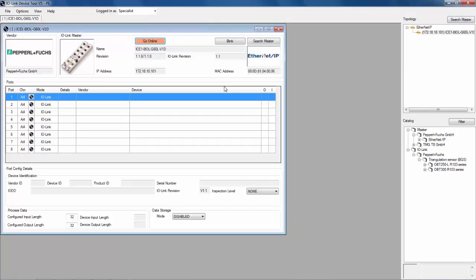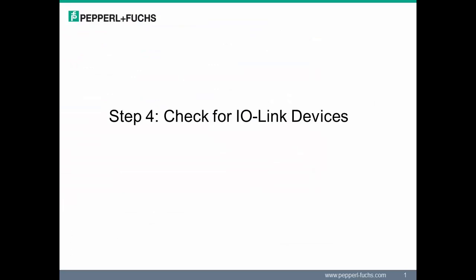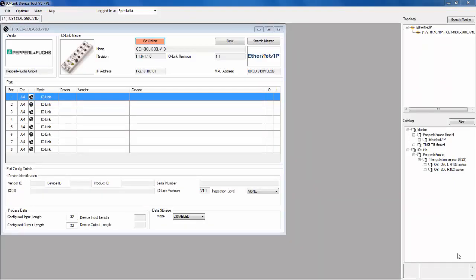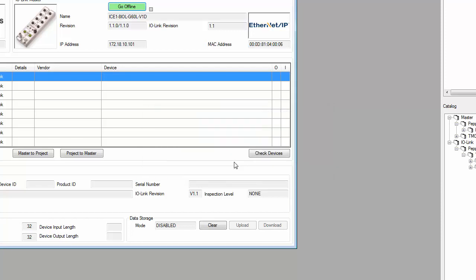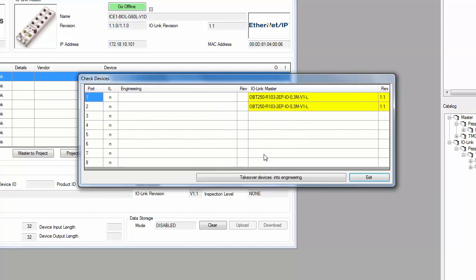Step 3 requires us to search for our IO-Link Master. Having the identity recognized in the catalog, we initiate a search of the Master by clicking on the option in the upper right corner. As the search is performed, our IO-Link Master is discovered. Now let's check the IO-Link devices connected to the various ports on our IO-Link Master. To initiate this search, click on Go Online, synchronize the configuration if prompted, and check the devices on the various ports.